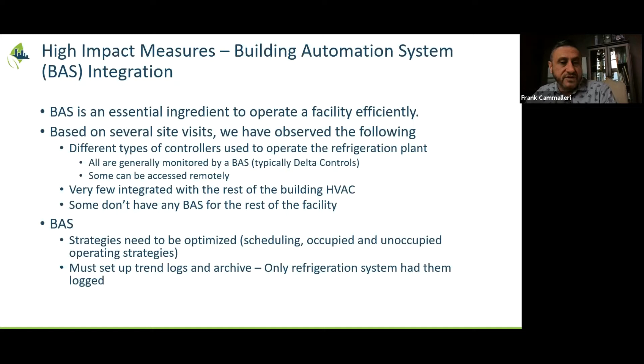One of the key things that typically surprises us and the operators is, during our site visits, we talk a lot about asking the operators how they operate the facility. And then it's when you show the trend logs that you see that it often doesn't operate the way one thinks. And again, that's the value of the trend logs. They don't lie. They tell you actually how it operates. So it's just good information, and it's really essential for making the building as efficient as it can be.